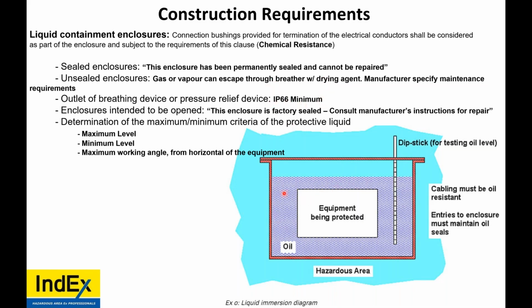So the outlets or breathers shall have an IP66 rating. Enclosures intended to be opened need to be identified with a warning. This enclosure is factory sealed. Consult manufacturer's instructions for repair. What they mean is when even they open it up to do maintenance, they kind of mean repair at the same time.